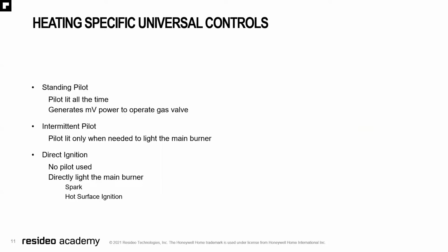Heating specifications for universal controls. As everyone is probably aware, standing pilot: pilot is lit all the time. Self-generates millivolt power to operate the gas valve and sometimes the thermostat, depending on the millivolt, if it's just a standard thermocouple or if it's the thermopile. Intermittent pilot: the pilot is lit only when there is a need to light the main burner, continues to be on through the call for heat, and then turns off at the end of the call for heat. And direct ignition: there is no pilot used. You directly light the main burner either through spark or some form of hot surface ignition.